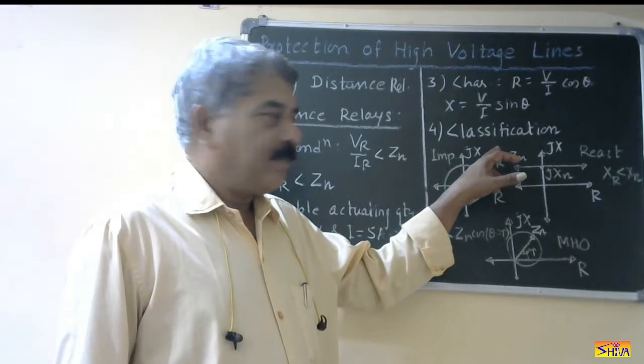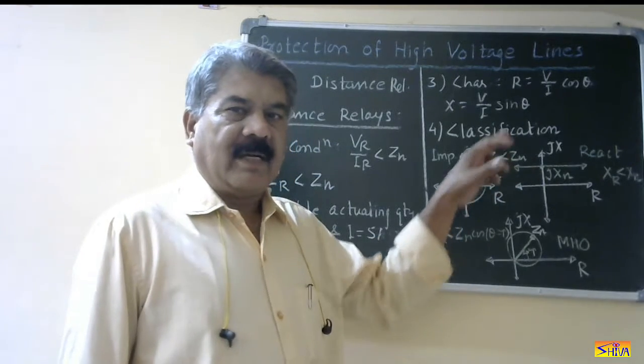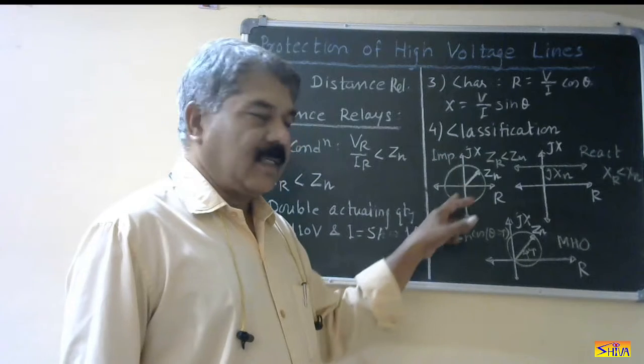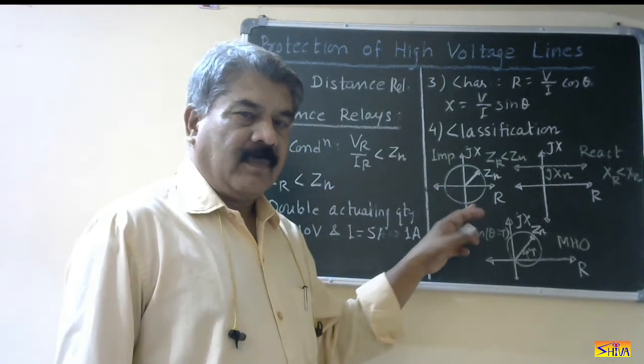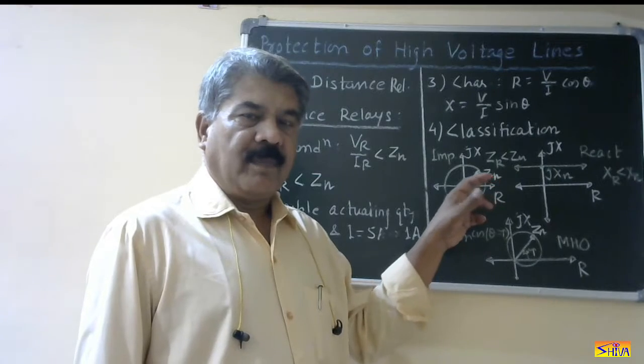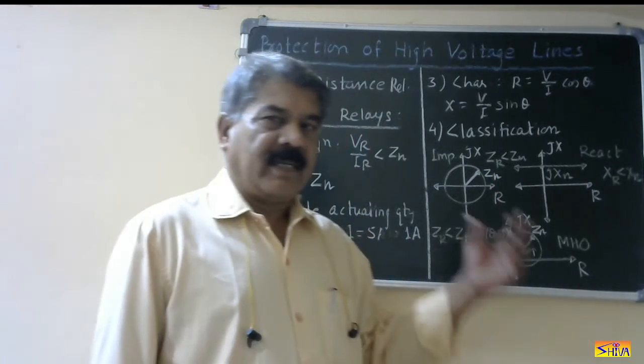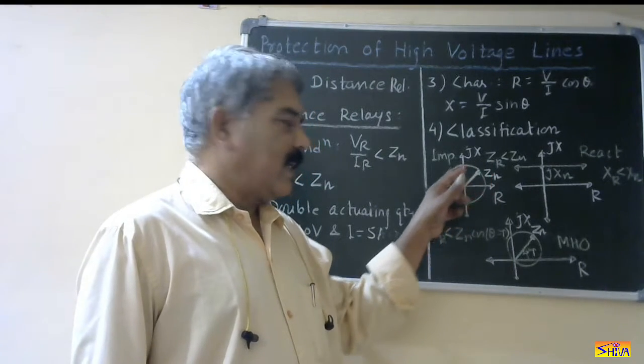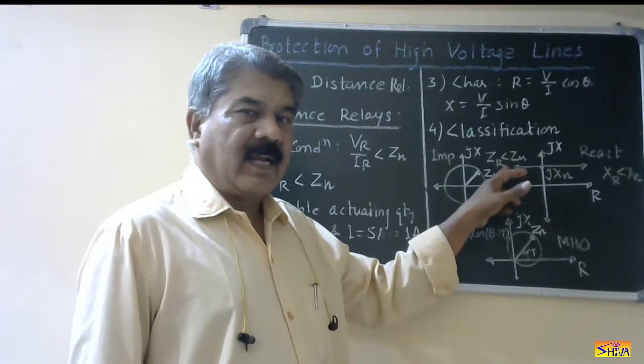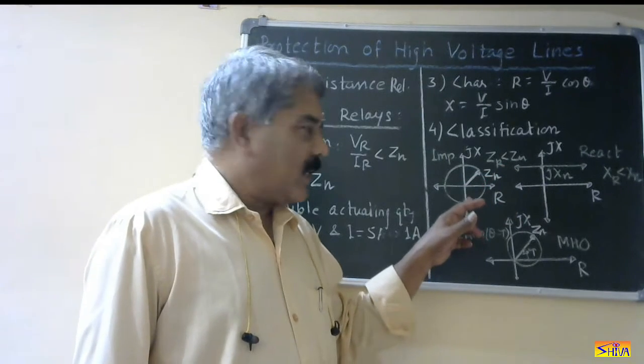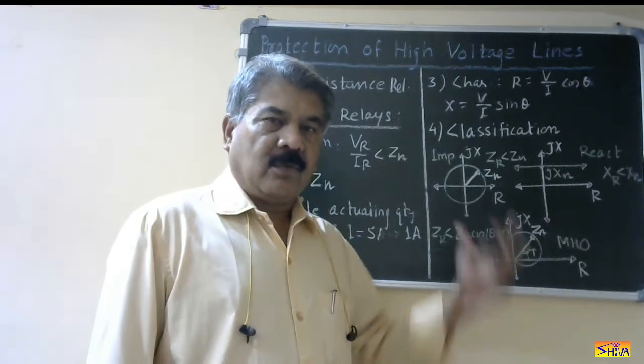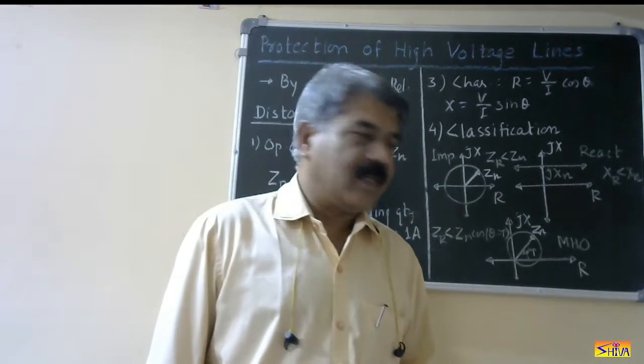Then the classification of distance relays: distance relays are classified according to their characteristic in the R-X diagram, and we get three conventional characteristics. The first is the impedance relay. The characteristic of the impedance relay is a circle having its center at the origin and its radius equal to the impedance setting of the relay, Zn. The operating condition is Zr should be less than Zn. All the impedance vectors whose tip lies inside this circle will operate the relay, so inside this circle is the positive torque region or operating region.